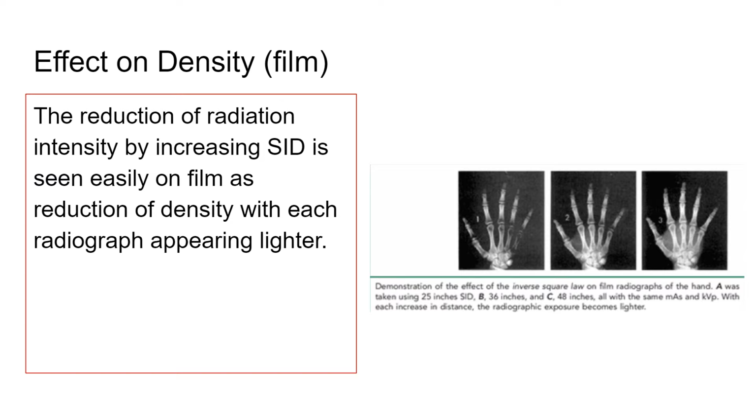So you've got to look at that exposure indicator. Have you seen it at the hospital? It depends if you're using CR or DR. If you're using DR, it shows up on the screen right there with your image. If you're doing CR, then obviously it's not going to show up at the exposure. It's going to show up wherever the processing unit is when it comes up. But technologists should be looking for that, or maybe it's color coded. Sometimes it's a yellow, a red, and a green to show you the range that you're in.